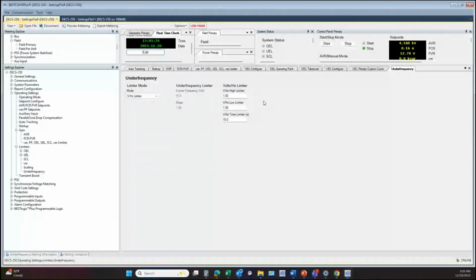The difference is that this is always going to be active. You're not defining a knee point. You're just defining the maximum ratio between volts and your frequency on a per unit basis. So you don't want the volts per hertz limiter set to 1.0. Normally 1.05. Maybe you might set the high to 110, and then there's a delay. So it will allow you to get to 110% ratio between voltage and frequency. But after 10 seconds, it will pull you down to the 105%. So that is, at your rated frequency, it will allow your voltage to go up as high as 105 per unit, or 1.05 per unit voltage, 105% of your rated voltage.